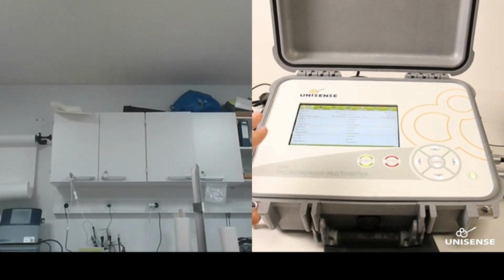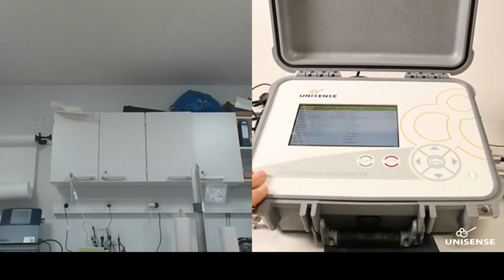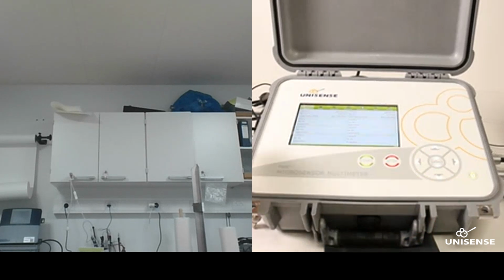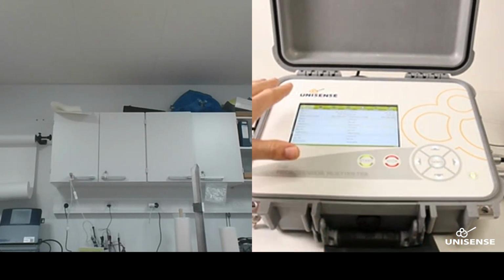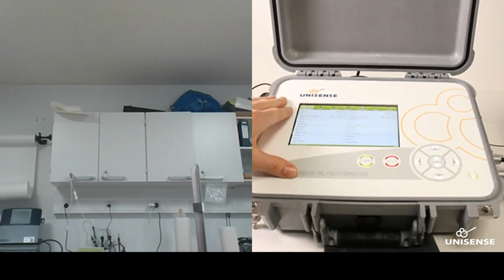So the field multimeter is a battery-powered thing. You can run it on a power supply if you want. It can also run up to 20 hours on battery. It has 8 channels for sensors, so 5 amperometric, 2 potentiometric, and 1 temperature sensor. It can be operated by the software fully, so the only thing you need is the on-off button, but you can also operate it totally on its own, so a standalone instrument.